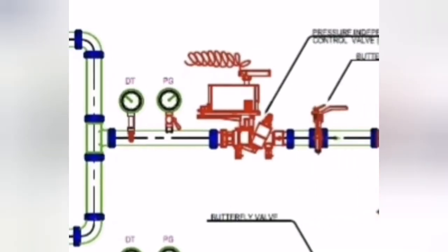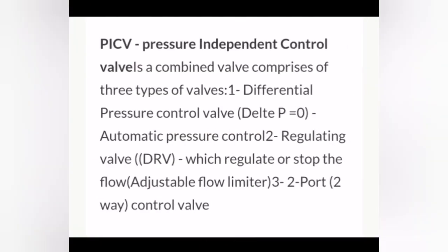And the third one is the PICV valve. The PICV valve has a very important role in our chilled water system or any refrigeration system. PICV is the pressure independent control valve. I will explain what the function of this valve is. PICV, pressure independent control valve, is a combined valve comprising 3 types of valves. It has 3 functions. One is the differential pressure control. Second one is the automatic pressure control, which means regulating the flow, like a DRV, double regulating valve. And third one is the 2-port control valve, like your actuating valve.